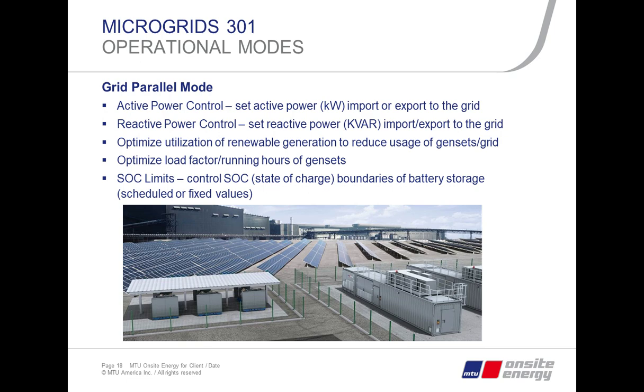One thing that's important for us as genset guys is really optimizing the run hours of the genset. That probably means we can do multiple generators of different kW on the same plant, spreading the run hours across those engines. If engine 1 runs during different parts of the day and engine 2 runs at other times, we can spread those run hours out and extend the overhaul life on those engines quite a bit.